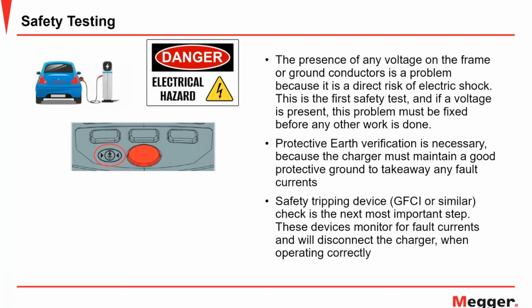And that needs to be the first test before doing anything else, because if there's voltage present, you need to stop, be very careful, and fix what the problem is. The next most important test is the protective earth connection, which is basically a bonding test between the frame and an earth point or a grounding point. That is important because any fault currents, any issues need to be drained or sent away from people touching it.